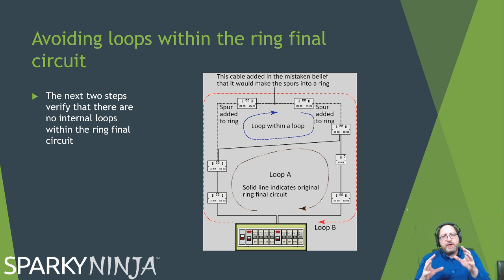And this creates what we call the figure of 8. So the line going out that way connects to the neutral coming back, the neutral going that way connects to the line coming back, and it's out of the board, so it's like a floating figure of 8 in the system. We're then going to go around the system and measure from line to neutral, or line to earth, depending on which test we're doing, at each socket.